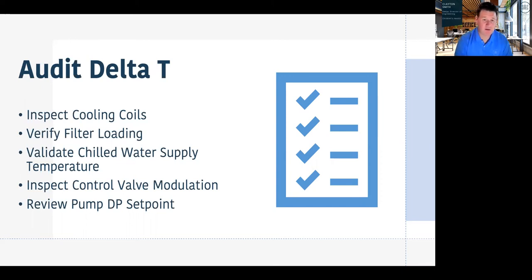Inspecting control valve modulation. How often do we see an issue where we're not cooling a space appropriately, or even overcooling a space, and find out that the control valve is not operating at its full range? It's operating too much, so it's not actually throttling down the flow like it should. So we're overcooling or driving more demand on the chilled water plant than is necessary. Or on the other side, we have a hot problem, and that modulating valve isn't doing what it's supposed to.